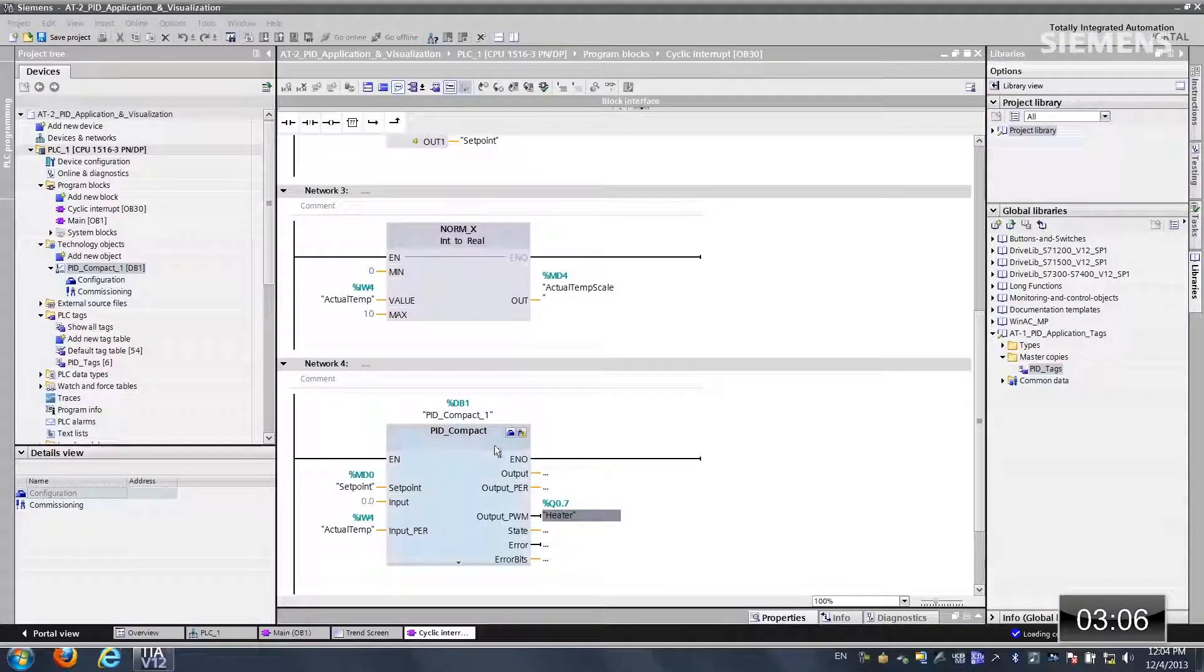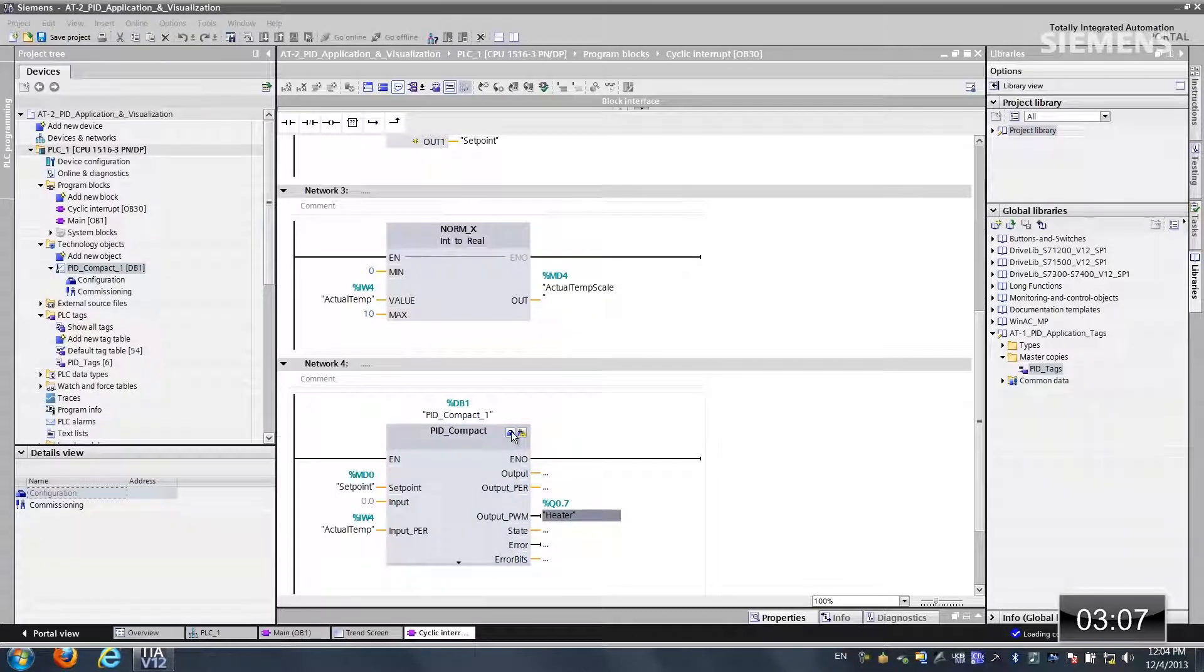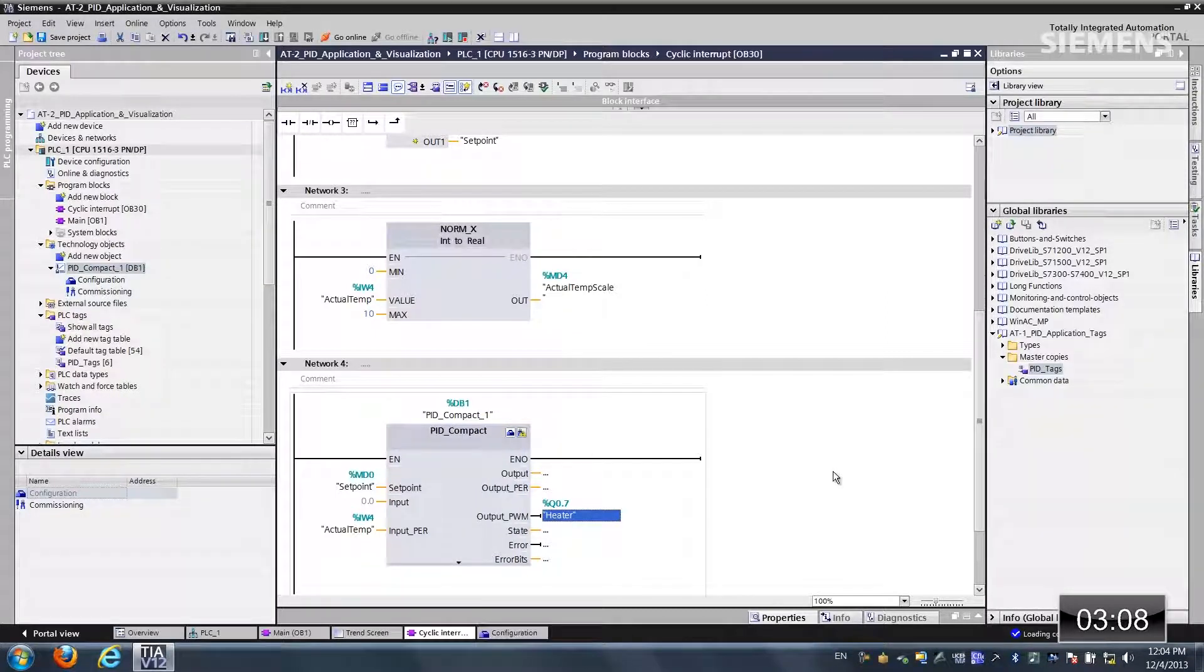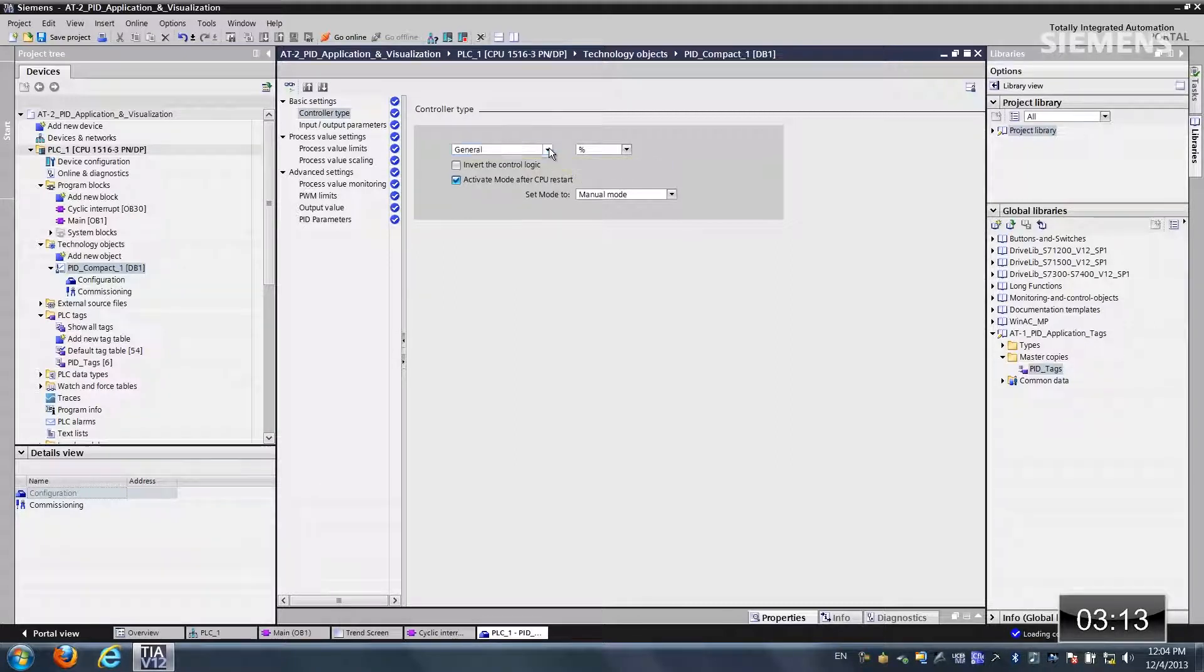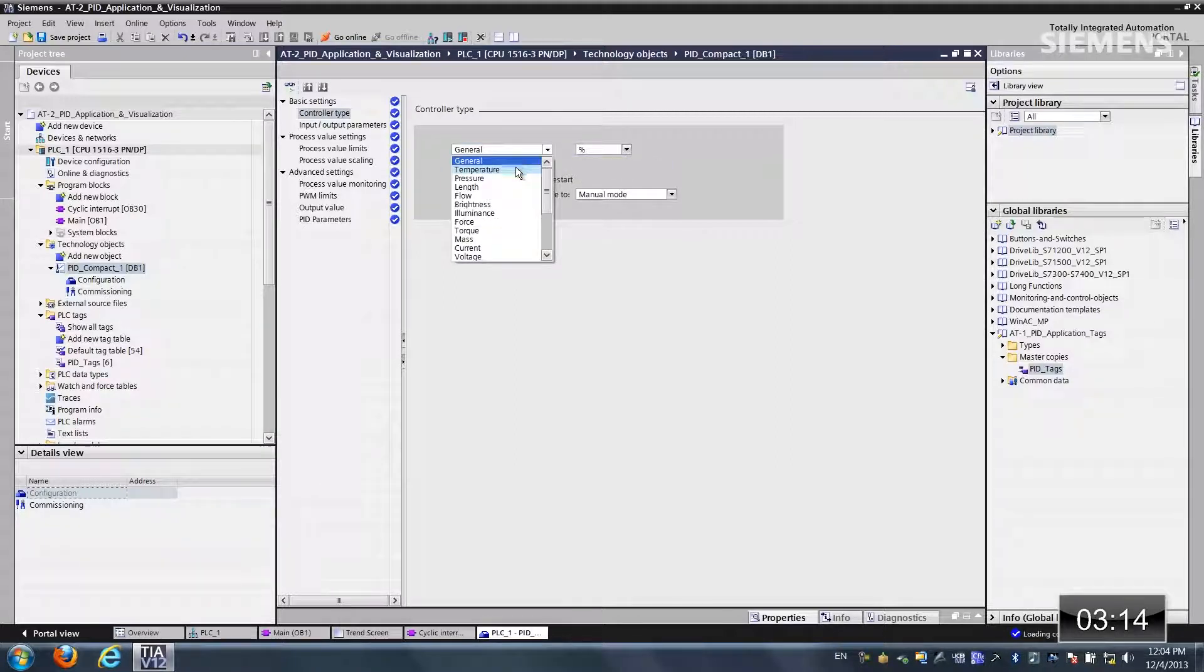The next step is doing the actual configuration of the PID. In the upper right-hand corner of this block, you see a little tool box. Click on that. We get a dialog box of all the settings. The first step happens to be the actual controller type. Let's choose temperature and Celsius.